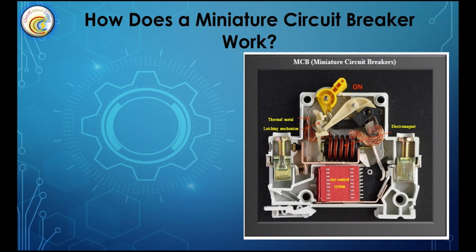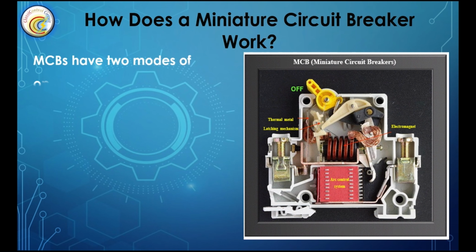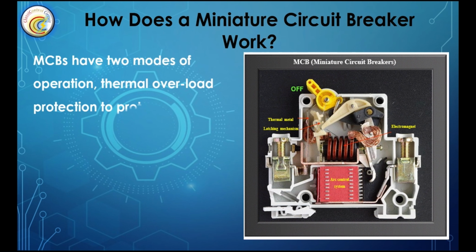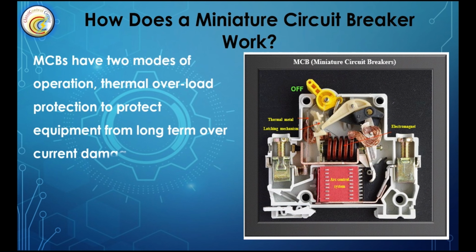How does a miniature circuit breaker work? MCBs have two modes of operation: thermal overload protection to protect equipment from long-term overcurrent damage, and magnetic short-circuit protection to protect equipment against very high fault current.